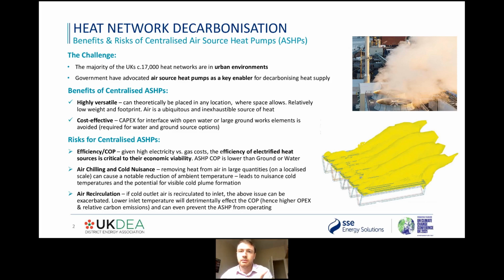The negative effect is that this will detrimentally affect the COP, because your inlet air temperature will keep reducing and reducing. Not only will that affect your economic viability, but it can also affect the heat pumps from operating. They will eventually reach a minimum inlet temperature or condensation temperature where the heat pumps will start to derate if the air temperature gets too low. So that's an issue that we've got to investigate and see if we can solve.